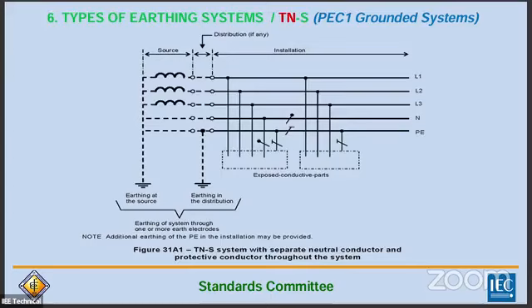Yung mga non-linear na loads natin, so merong neutral current. Yung PE, tawag natin protective conductor, because this is used for protection sa fault current. Diyan dadaan ang fault current mo, hindi dun sa neutral, so you have to always run a protective earth sa installation.